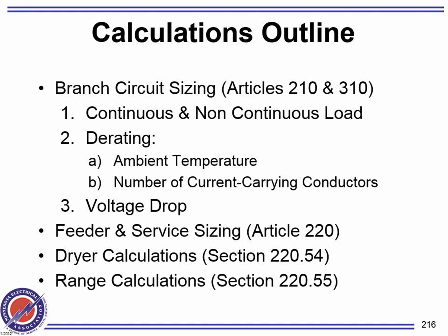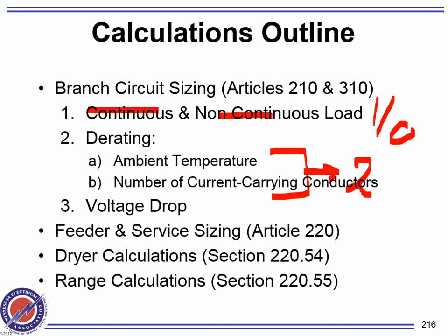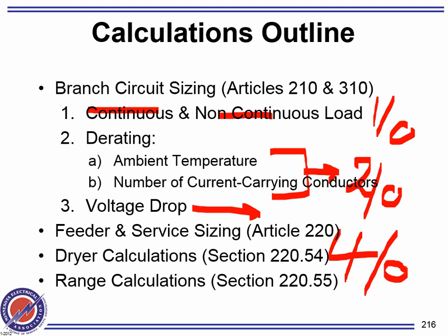Number one, suppose based on continuous and/or non-continuous, I came up with 1/0. Then I did my derating based on temperature, and I came up with 2/0. These are completely separate calculations, and have nothing to do with each other. Okay? And then the third separate calculation is voltage drop, and I came up with 4/0. Which conductor should I use for this service? The largest. Does that make sense?